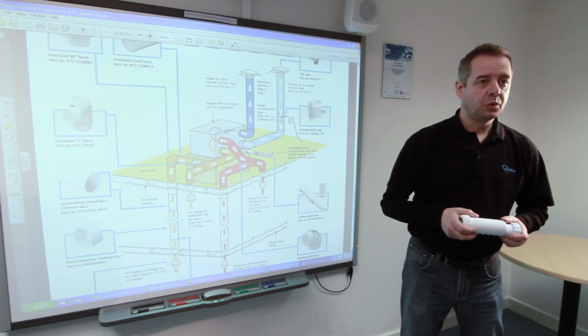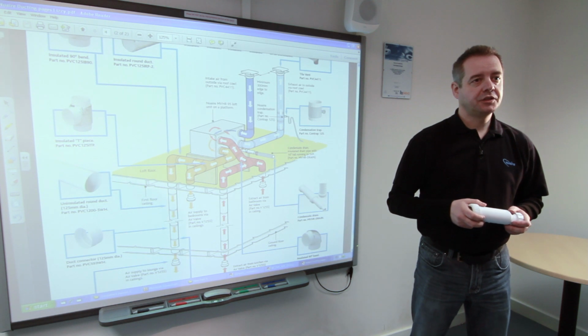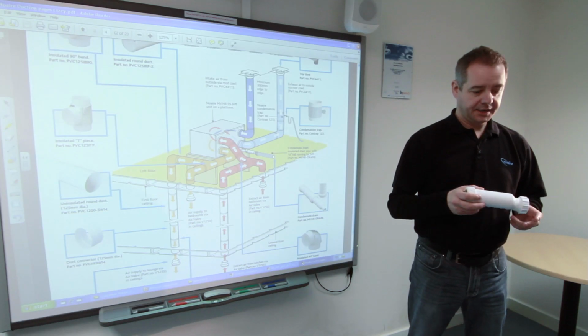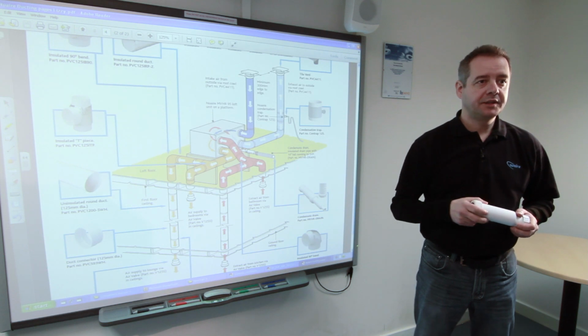The use of a waterless trap is very important in the installation of a heat recovery system for two reasons. One reason is to prevent smells from coming back up from the soil stack where the condensate pipework should be terminated. And another reason is because there's negative pressure within the fan. If the trap isn't present, it can stop the condensate from escaping the unit and actually build up inside the unit and cause damage to the building.